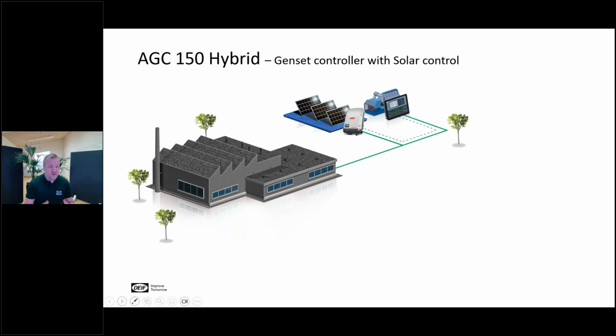And I will not repeat what Christoph said, but it is very important not to over-dimension the PV part, because that could put the genset in a situation where it's again not running very optimally, but you could even destroy the genset sometimes if you do it in the wrong way. So it is important to have a controller on board.